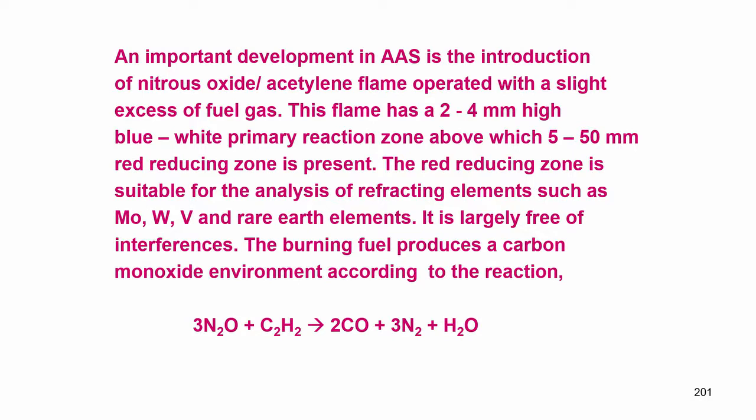An important development in atomic absorption spectrometry is the introduction of the nitrous oxide and acetylene combination. This flame is operated with a slight excess of fuel gas, which means the flame would be red in color. So, you have to adjust the flow rates of nitrous oxide and acetylene to get a reddish flame.